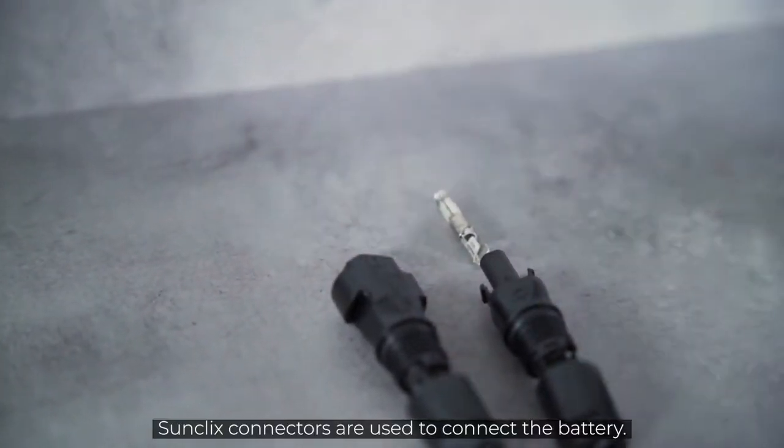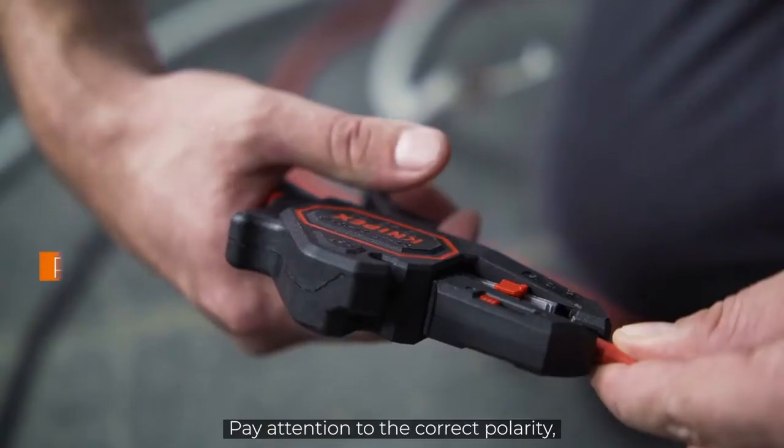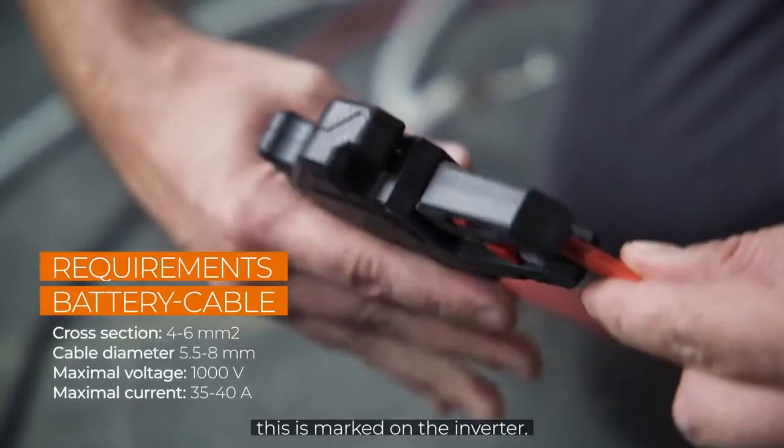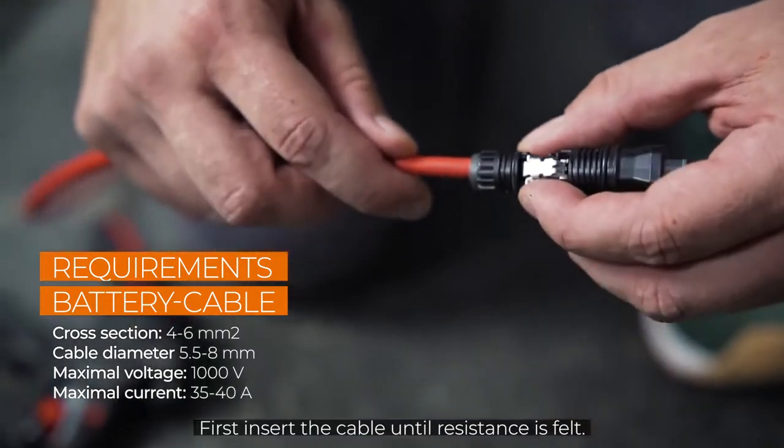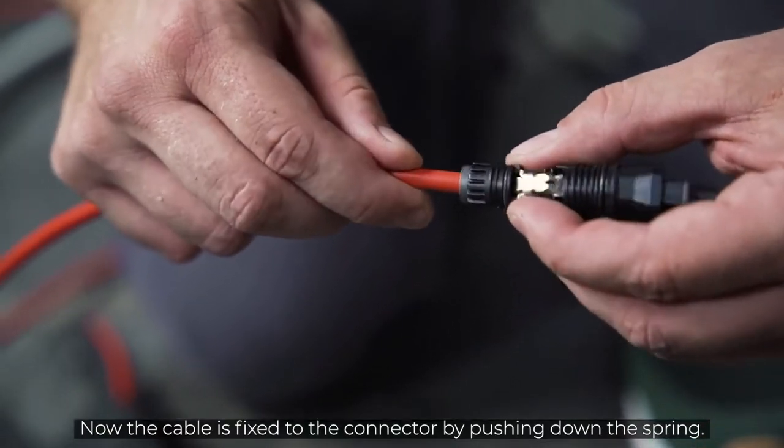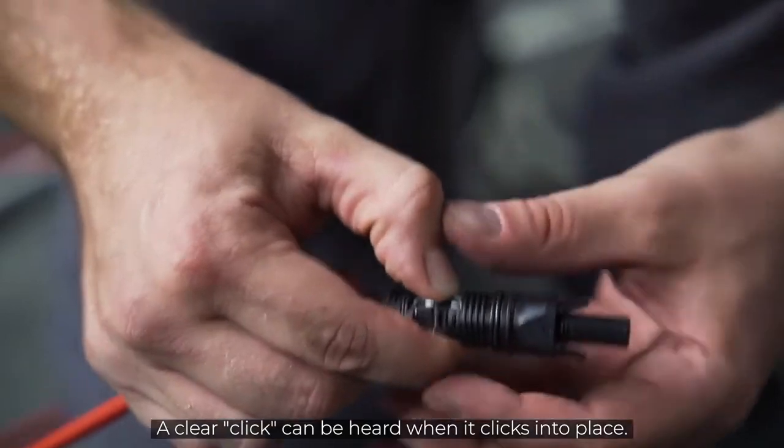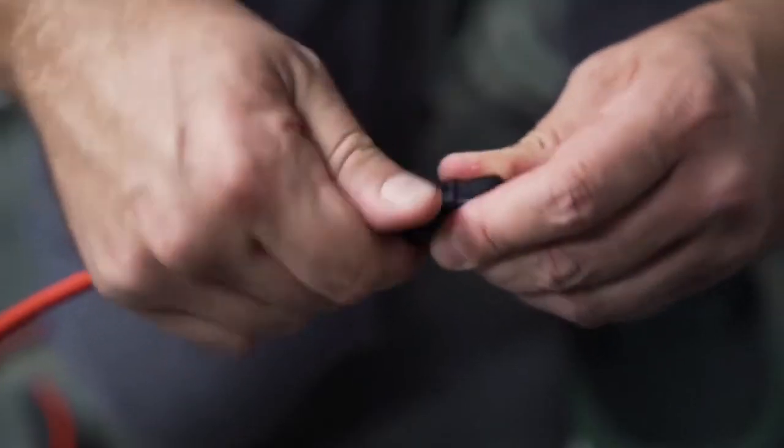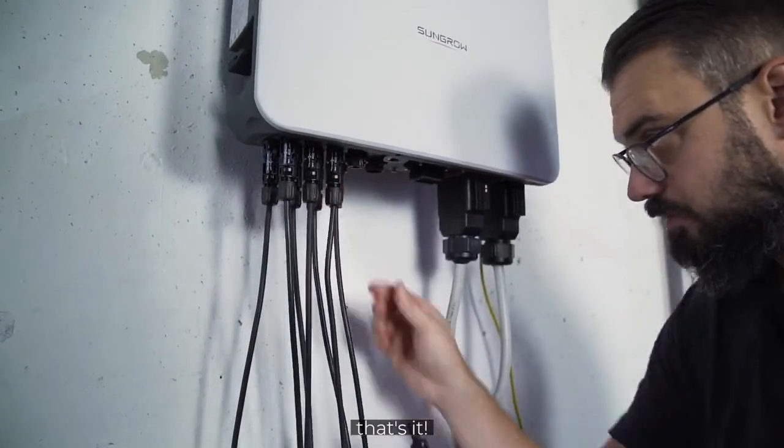SunClix connectors are used to connect the battery. Pay attention to the correct polarity. This is marked on the inverter. First, insert the cable until resistance is felt. Now the cable is fixed to the connector by pushing down the spring. A clear click can be heard when it clicks into place. Tighten the plug. Plug it in. That's it.